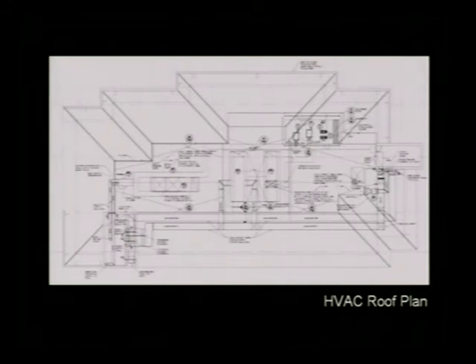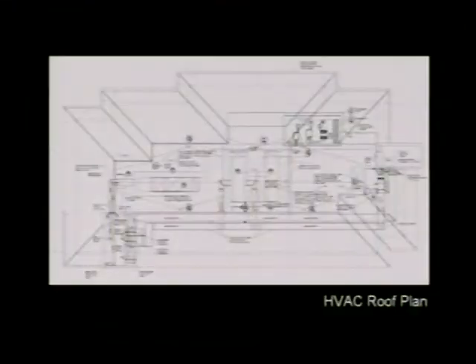We're able to actually use a smaller unit with less amount of air so we can use that air in the west in the afternoon and the east in the morning as the load changes around the building. The unit that's running east and west is the first floor VAV unit that provides the cooling for the first floor. And then there's another little unit, that RTU4, having a nice open, airy, fun stairwell on the south with lots of glass, required a little air conditioning unit, so we put that unit on to take care of that.